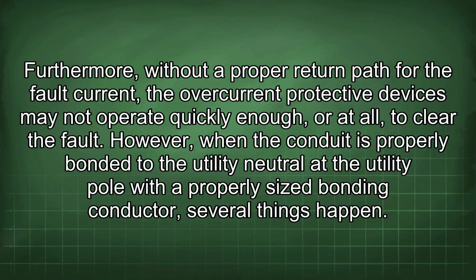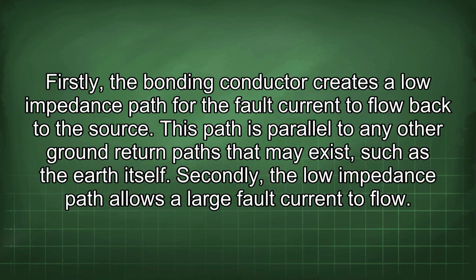However, when the conduit is properly bonded to the utility neutral at the utility pole with a properly sized bonding conductor, several things happen. Firstly, the bonding conductor creates a low impedance path for the fault current to flow back to the source. This path is parallel to any other ground return paths that may exist, such as the earth itself. Secondly, the low impedance path allows a large fault current to flow.